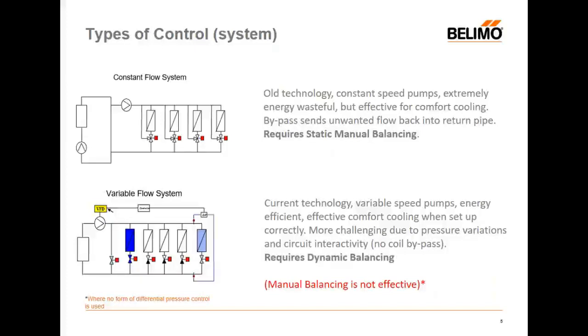So we don't have now three-way valves, we employ two-way valves. But those valves now have a much more difficult job. And if I put manual balancing valves here, they'll work quite well in design condition, but they'll only work in design condition because the pressure drops across the control valves will change as the flow rates change. And another feature of variable flow systems with this type of control solution is, of course, we might suffer interactivity between the circuits.